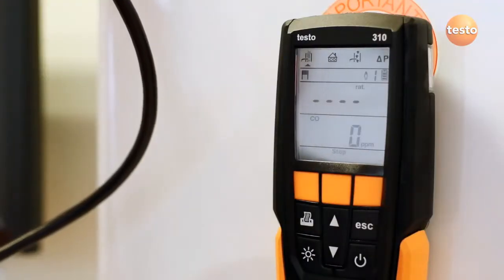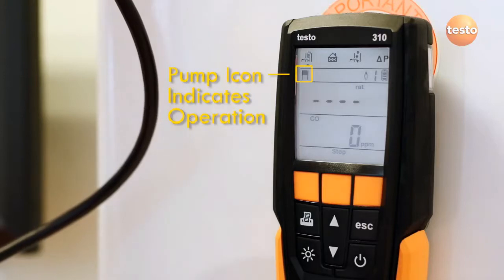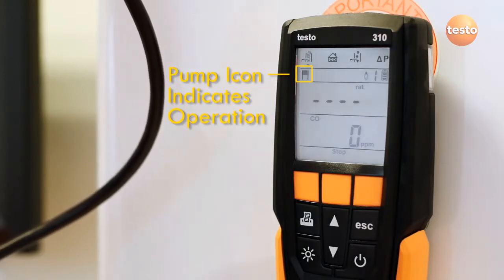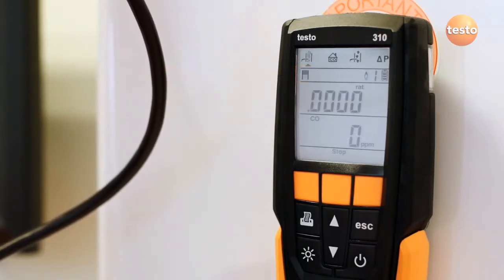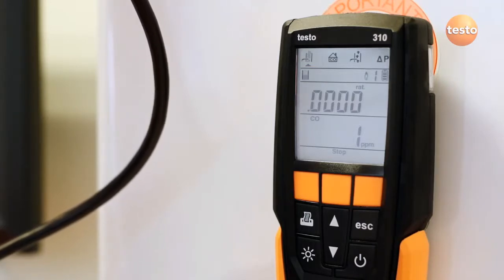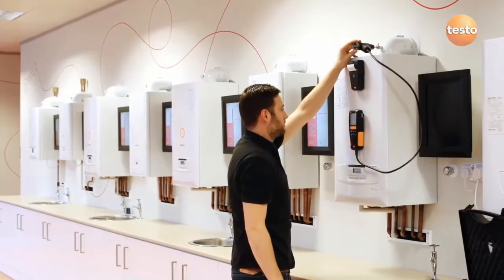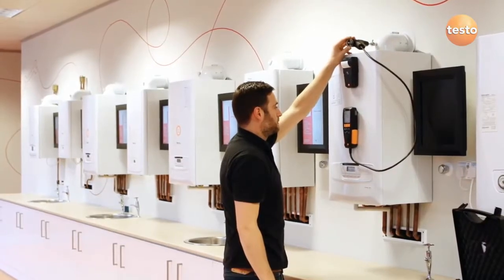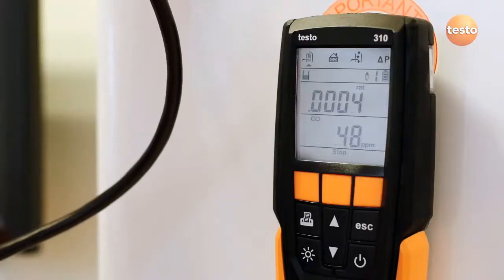Press Start to begin taking a measurement. The pump starts running, indicated by the icon at the top left of the display. The analyzer is now measuring the flue gases. The display shows ratio and carbon monoxide. Using the up and down arrow keys, the display can be configured to show any parameter such as carbon dioxide, excess air, efficiencies, flue temperature, or oxygen.